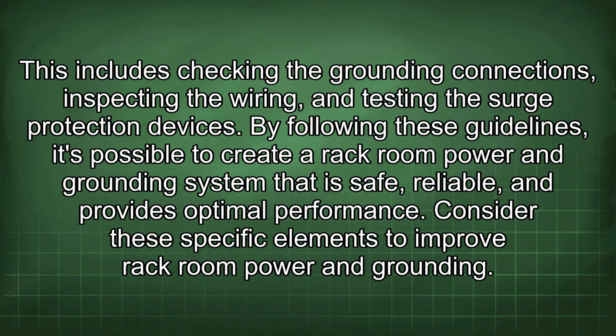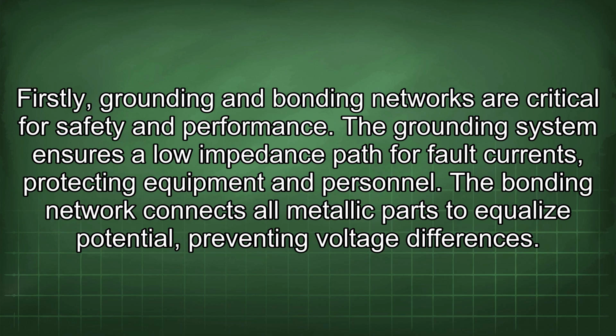Consider these specific elements to improve rack room power and grounding. Firstly, grounding and bonding networks are critical for safety and performance. The grounding system ensures a low impedance path for fault currents, protecting equipment and personnel. The bonding network connects all metallic parts to equalize potential, preventing voltage differences.